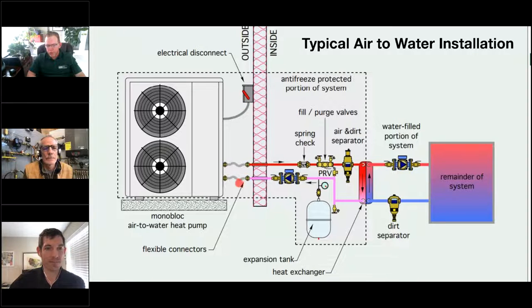And then the other thing that's worth noting is these right here. So these are braided stainless steel hose connections, and depending on what jurisdiction you're in, they'll serve a different purpose. Like I'm sure in California, they'll want these for earthquakes and other things. We want to see them everywhere because we don't want you running PEX tubing directly to a compressor-bearing unit. What will happen is that if the pump ever failed, this unit could still be running. The water could become stagnant, flash to steam, and then we rupture the piping. So it gives us that flexibility. It eliminates the noise issues, which is the other thing: as the compressor's running, this will not allow vibration to come back into the house and cause any noise.